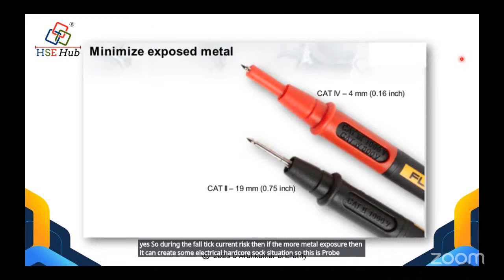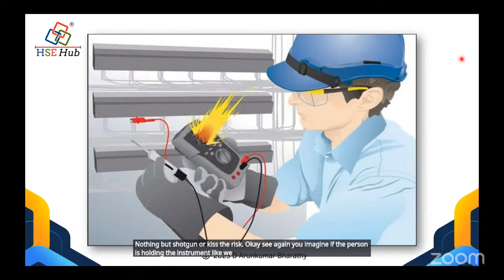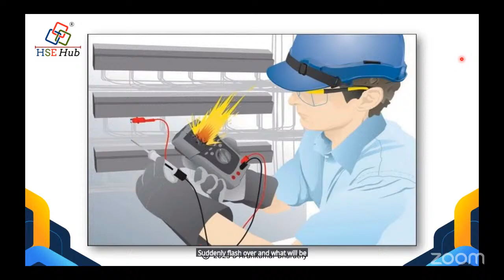So the equipment rating should be equal to the test lead rating - it should not be interchanged. I may have an instrument with category 4 rating and all certification, perfectly fine, but if it is used with a category 3 or 2 probe, the risk is inevitable. What is meant by risk? Nothing but shock and arc is the risk. Imagine if the person is holding the instrument like we hold our mobile phone in hand - if it's measuring like that and suddenly it explodes or flashes over, what will be the impact?